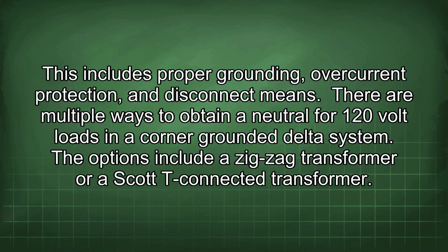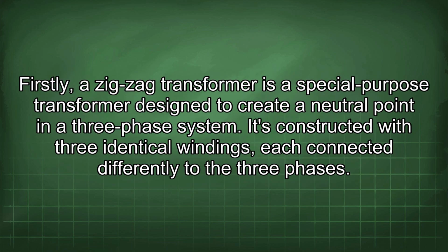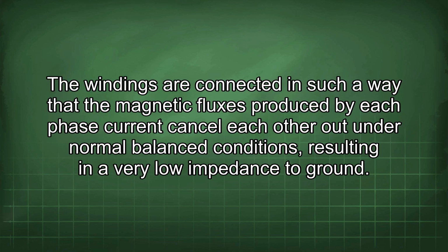There are multiple ways to obtain a neutral for 120 volt loads in a corner grounded delta system. The options include a zig-zag transformer or a Scott T-connected transformer. Firstly, a zig-zag transformer is a special purpose transformer designed to create a neutral point in a three-phase system. It's constructed with three identical windings, each connected differently to the three phases. The windings are connected in such a way that the magnetic fluxes produced by each phase current cancel each other out under normal balanced conditions, resulting in a very low impedance to ground.